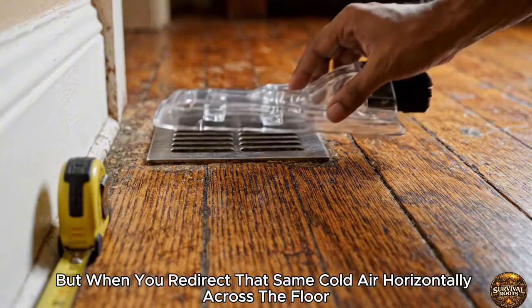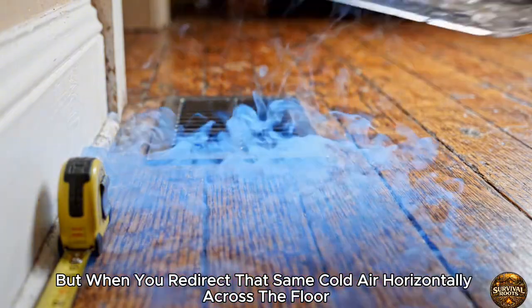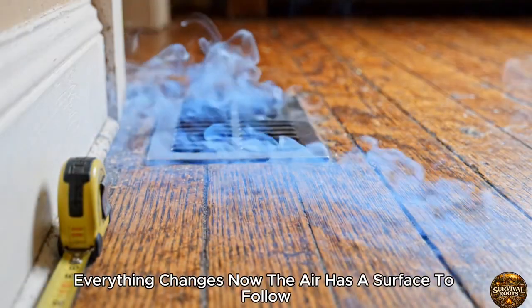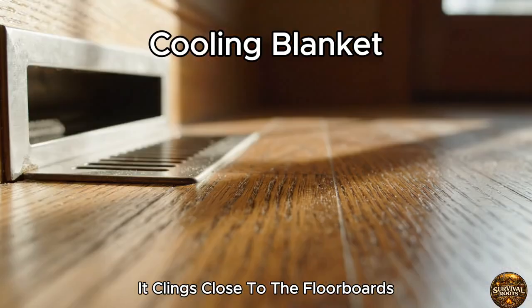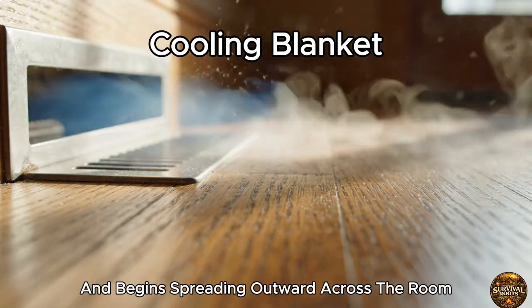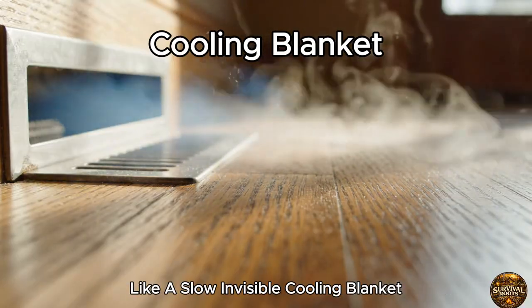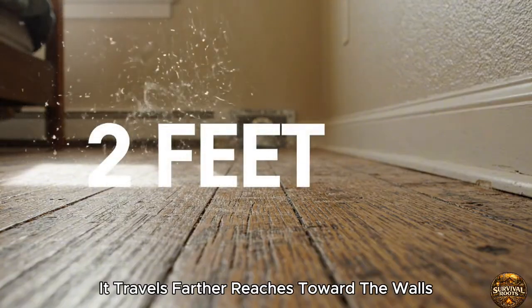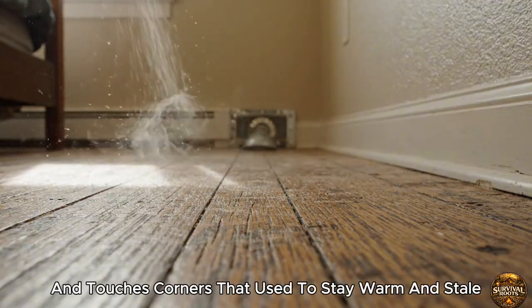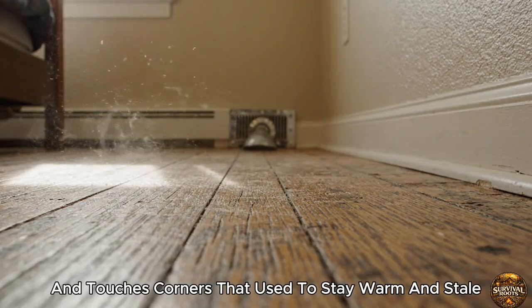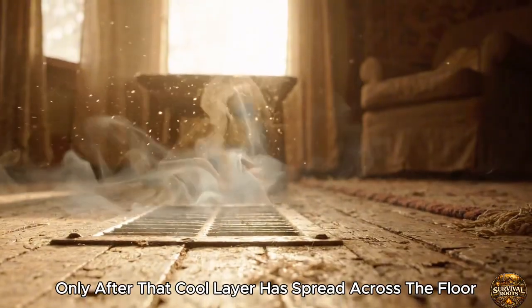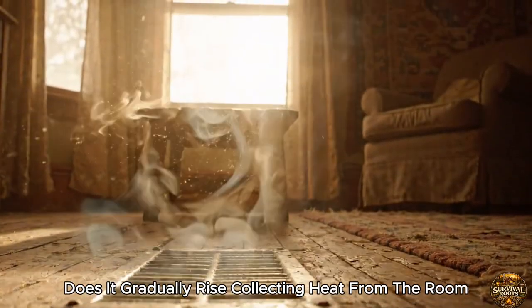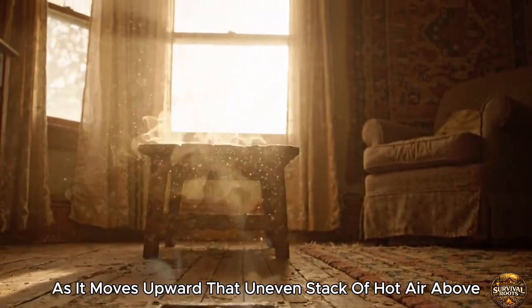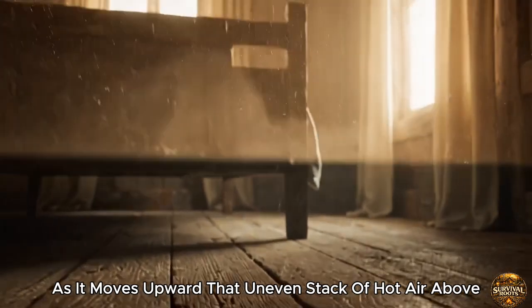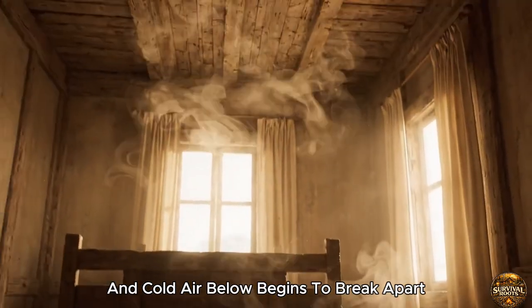But when you redirect that same cold air horizontally across the floor, everything changes. Now the air has a surface to follow. It clings close to the floorboards and begins spreading outward across the room like a slow, invisible cooling blanket. Instead of stopping 2 feet from the vent, it travels farther, reaches toward the walls, and touches corners that used to stay warm and stale. Only after that cool layer has spread across the floor does it gradually rise, collecting heat from the room as it moves upward. That uneven stack of hot air above and cold air below begins to break apart.